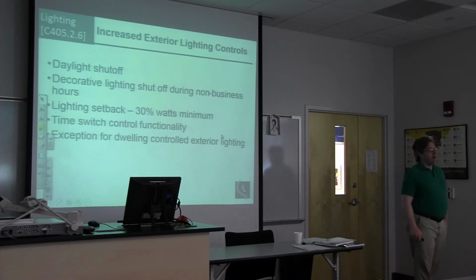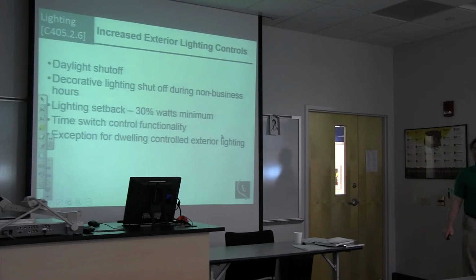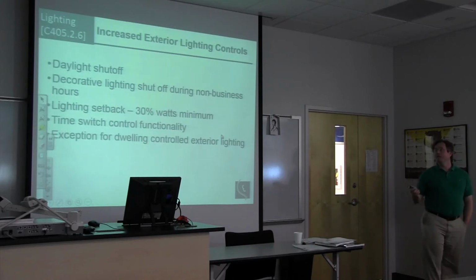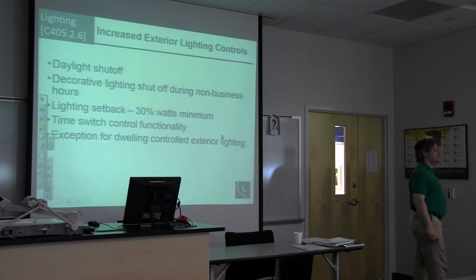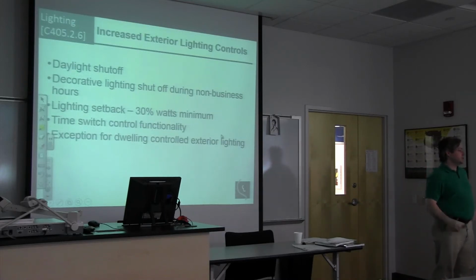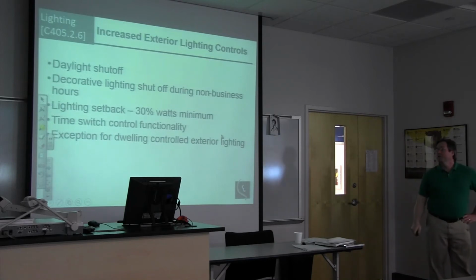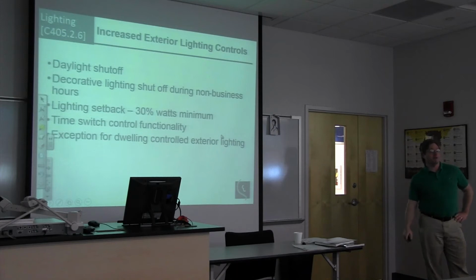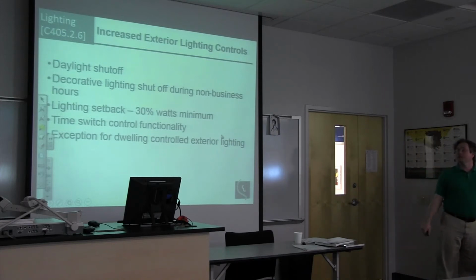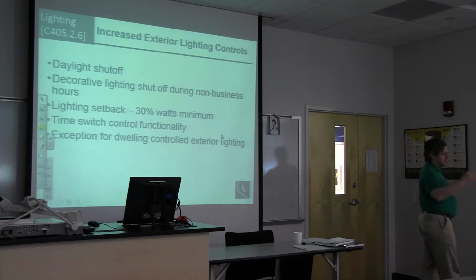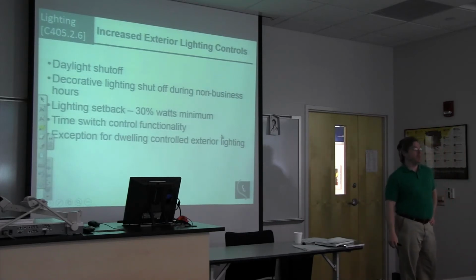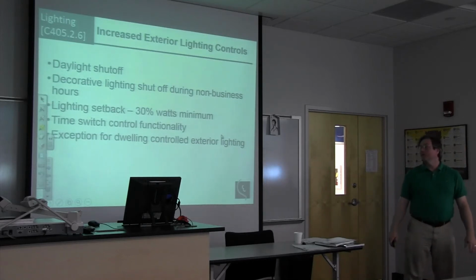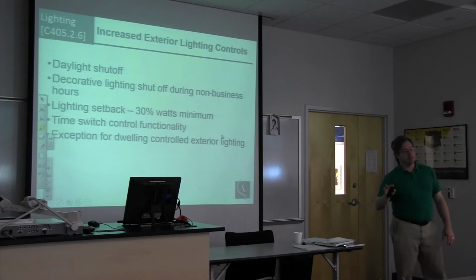Exterior lighting controls, they've now expanded what it has to do. So it has to have daylight controls and timer controls. Now this could be part of the same unit, or it could be separate. Two controls in series. One does daylight and one does timer control. But you now have to have both. They now have lighting setbacks, so anytime after business hours, I believe they let you have up to 1 hour after business to have your lighting on, but after 1 hour past business, your lighting has to come off. Now for security, they do provide some allowances for that too.